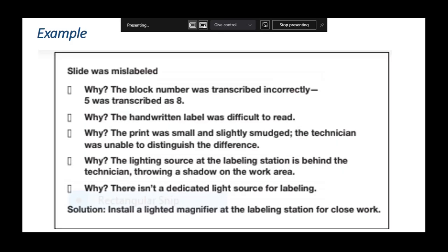Another example: a slide was mislabeled — why? Because the block number was transcribed incorrectly; instead of 5, it was written as 8 — why? Because the handwritten label was difficult to read — why? Because the print was very small and slightly smudged, so the technician could not distinguish between 5 and 8 — why? Because the lighting source was exactly behind the technician — why? Because there was no dedicated light source for labeling. The solution: install a dedicated light source. Not 'training was insufficient' or 'he should be more careful' — those are not root causes.